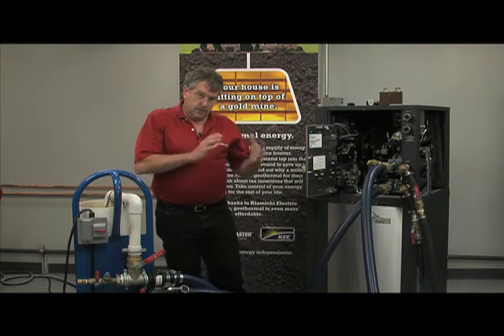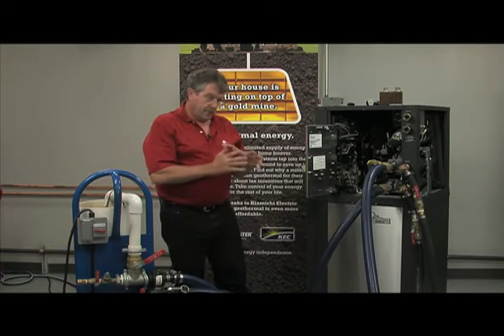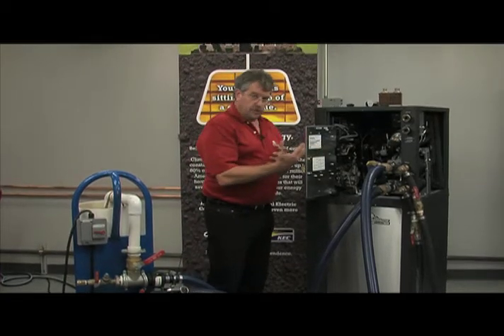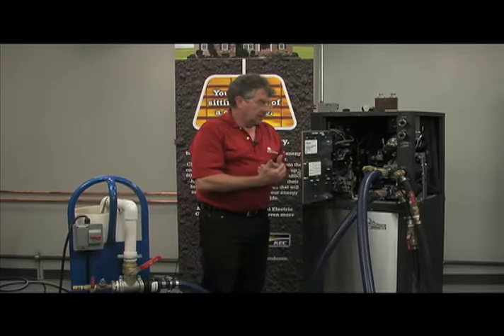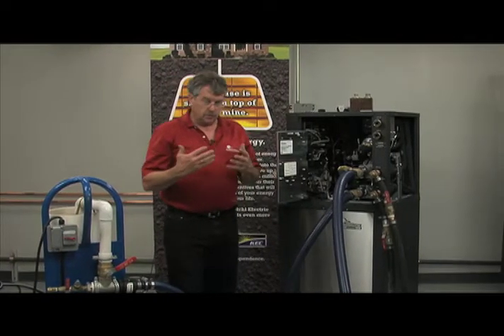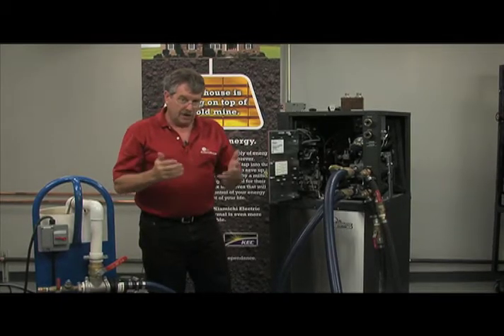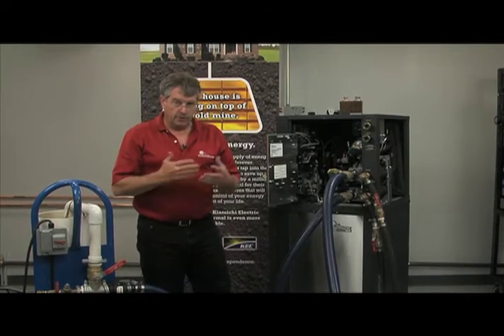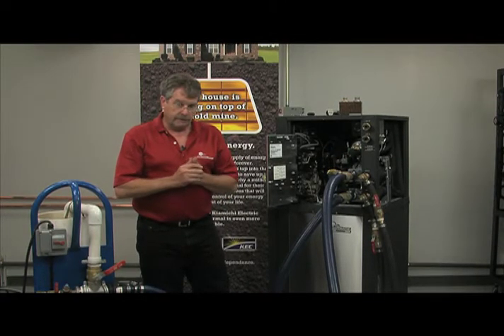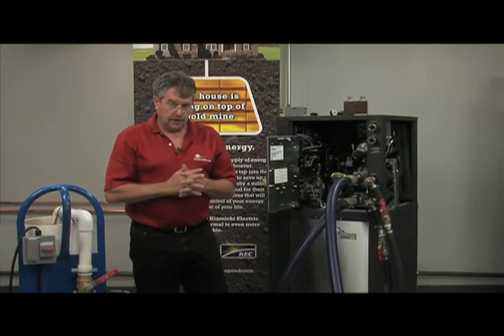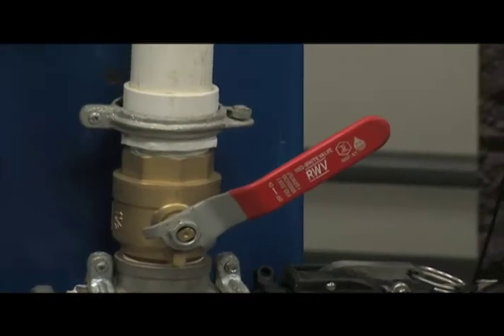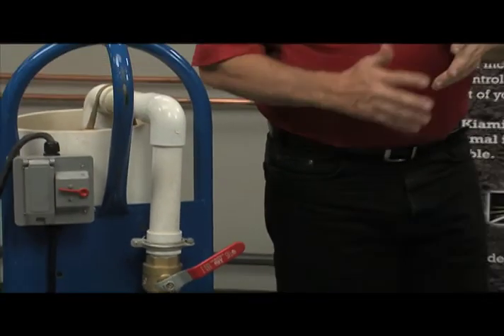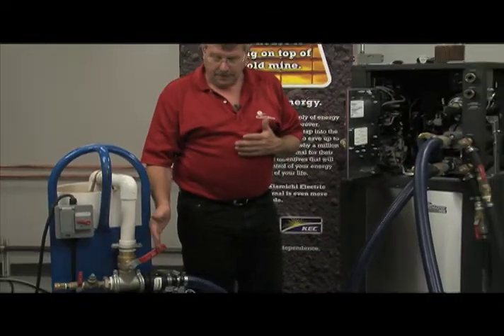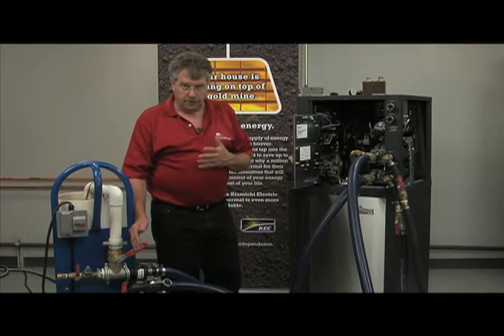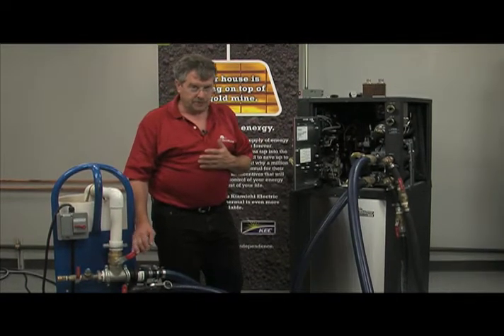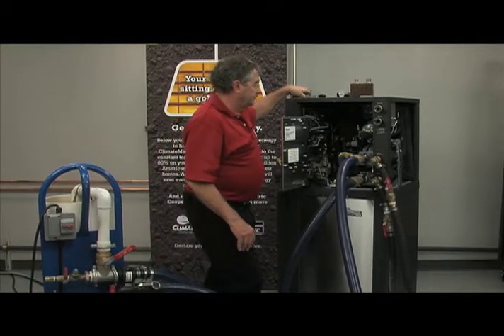So now I'm ready to actually do the last step here in the flushing procedure for the inside of the unit. That's I'm going to rotate those valves and actually mix both the loop and the unit fluid together. This is, guys, when you would actually take a sample of your antifreeze level, verify it, don't guesstimate, make sure you're actually using a hydrometer or a refractometer, and validate your amount of antifreeze should you need to add antifreeze in the location that you're in. So we're ready to rotate our internal vFlow flushing valves so that we're circulating through both the loop and the heat pump. Again, making sure that our return into the flush cart valve is remaining at no more than about 50% throttle. So we're going to go ahead and we're going to rotate these valves.